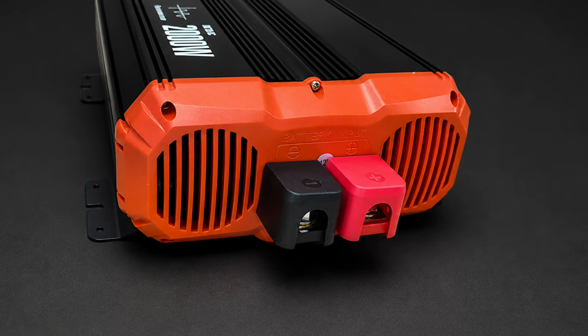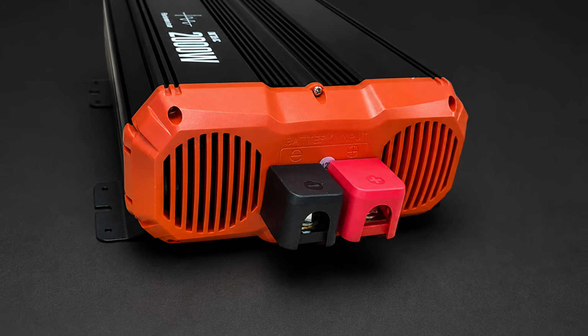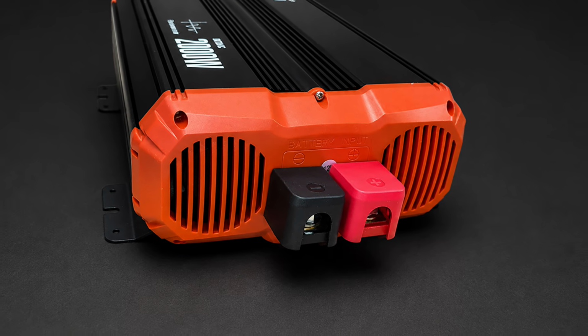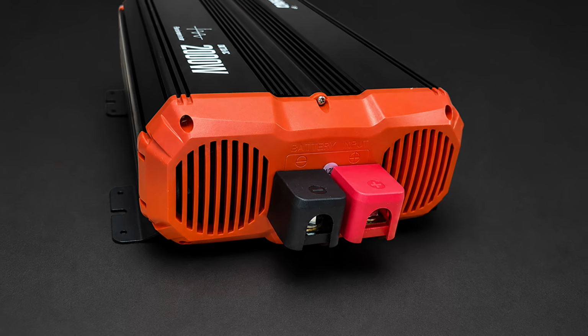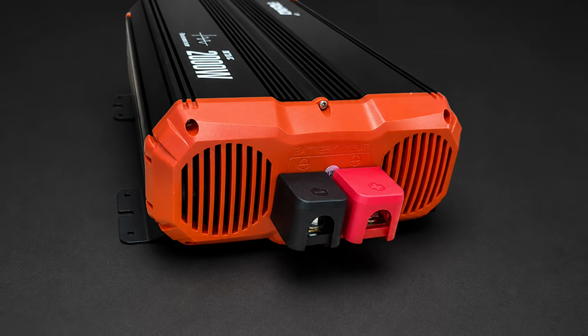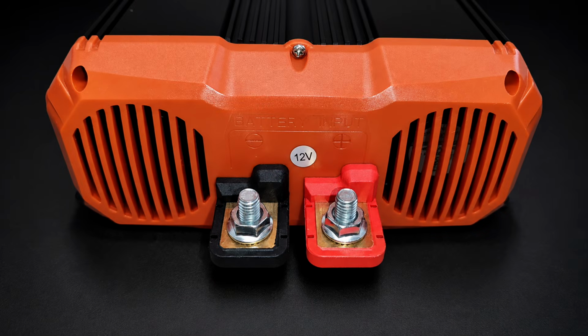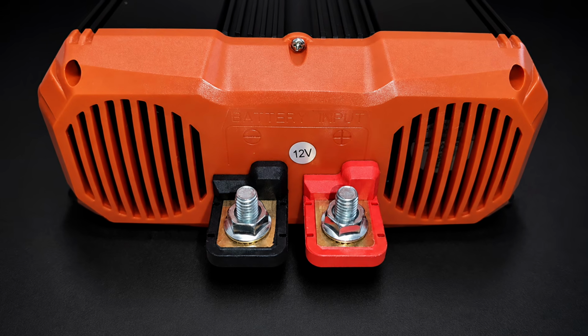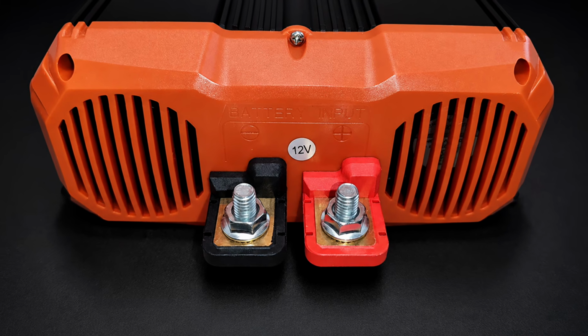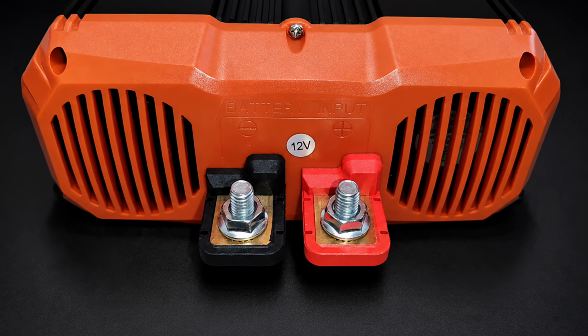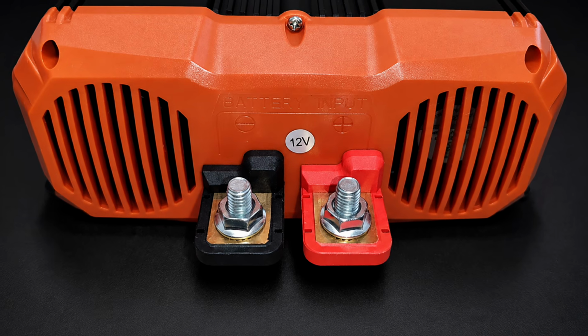For a 12-volt, 2-kilowatt inverter, this is an important point. The currents here are high, so an accidental short circuit at the input can be very unpleasant. The battery cables are connected through threaded studs with nuts. The polarity is duplicated both by color and by markings on the housing. Black is minus, red is plus.